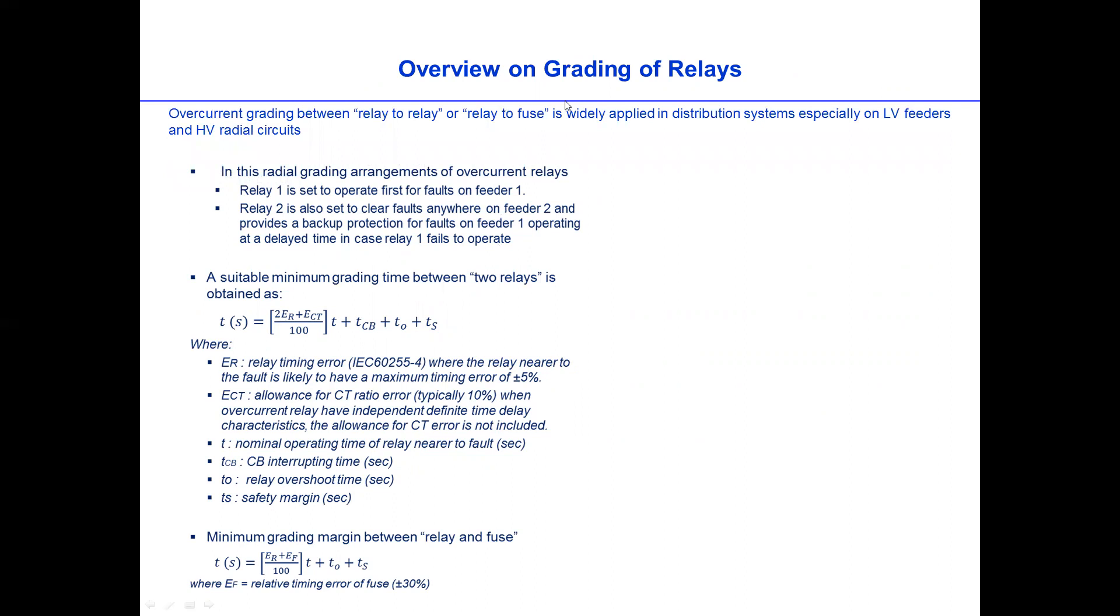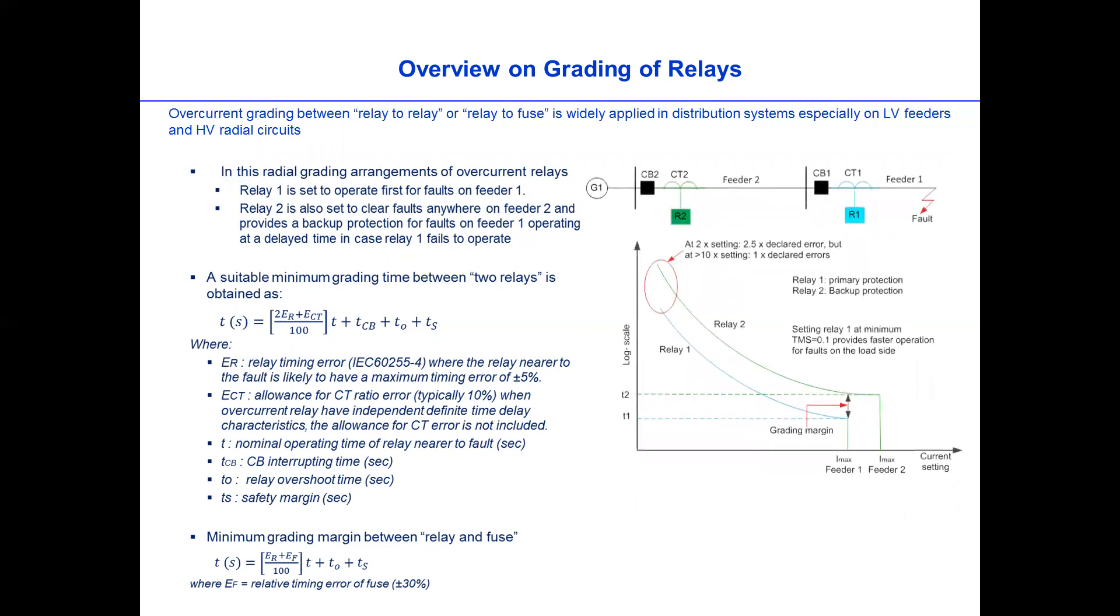So in this case again, we can look at overview on grading of relays. Grading relay using overcurrent protection is normally widely used in the distribution system, especially on LV feeders or HV radial circuits. We also use it in transmission system as a backup due to the difficulty in coordination. So if we look at the diagram on the right side, we have two relays on the single line diagram, which is radial network: relay 1, relay 2, where relay 1 is set to operate first for fault on feeder 1. And relay 2 is designed to operate for any fault in feeder 2 or any fault in feeder 1. But if relay 1 failed, then relay 2 will clear the fault at a delay time.